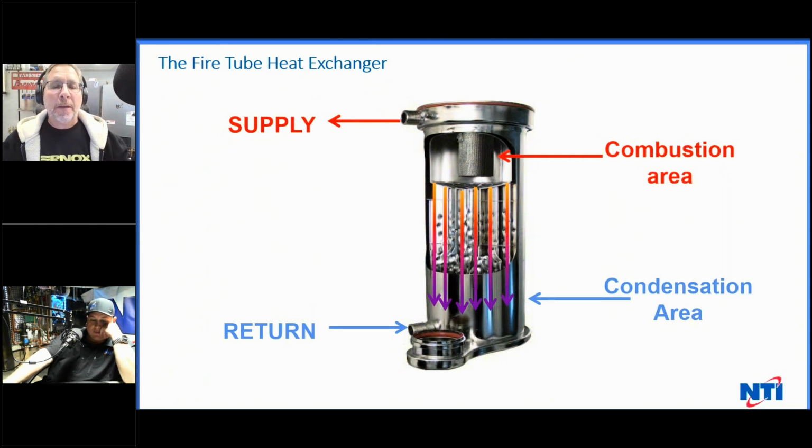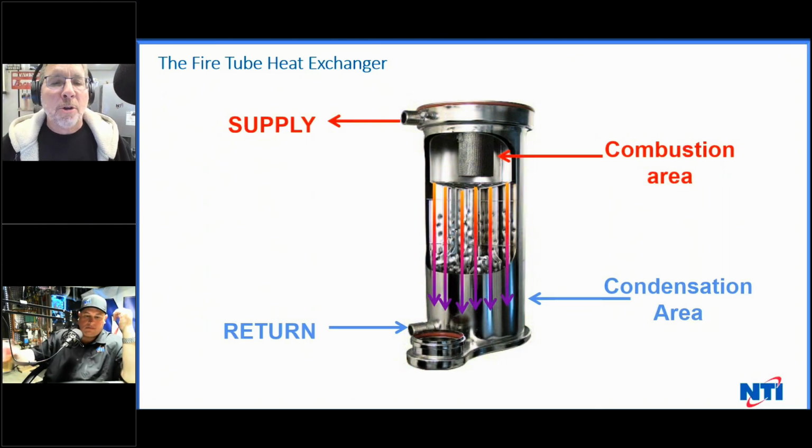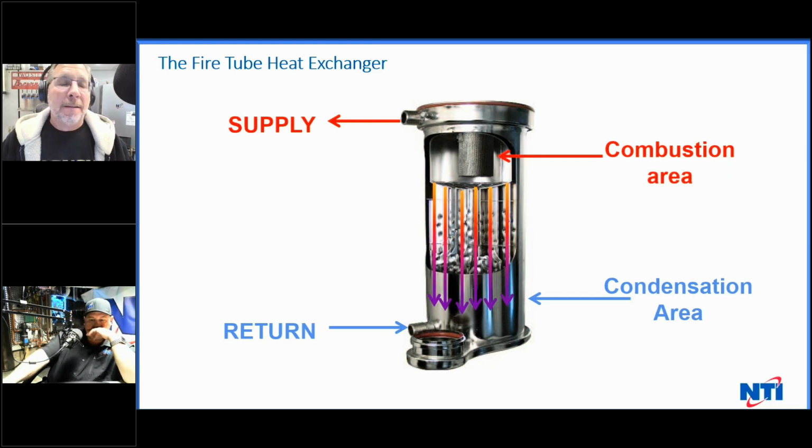Our spectrum of PVC is this: it comes white, it turns yellow, goes brown. We're increasing the temperature. From brown it goes pink, from pink it goes purple, purple then black, black then fire. Pretty easy. That's your spectrum, and I've seen it in the past 13 years in every one of those phases, which is why I'm dead set against using PVC for a venting product. It's no longer cheaper than Centrotherm. Centrotherm is less money than PVC, and it reduces your liability, but it's faster to install.